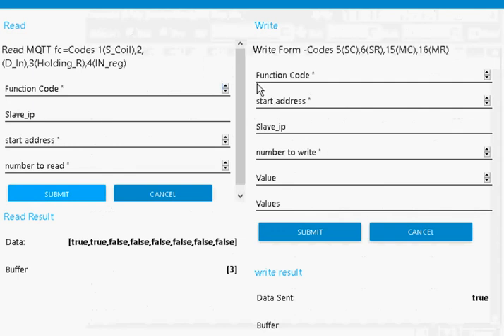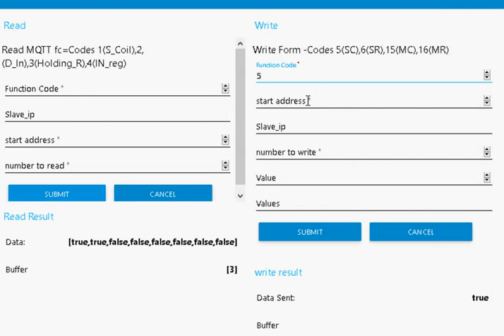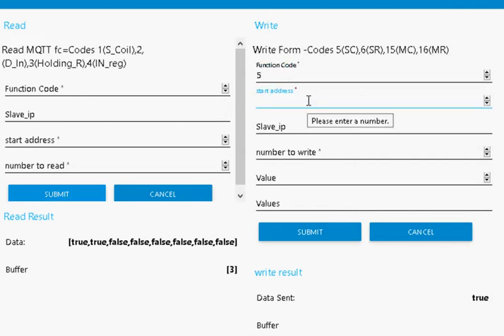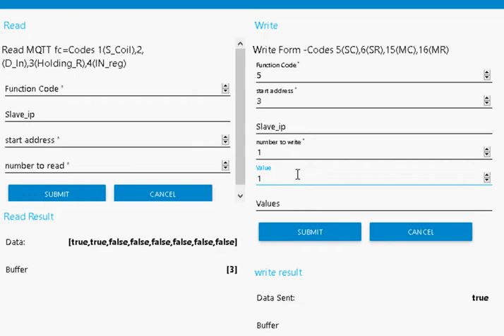Let me show you the writing. To write a single coil, I use function code 5. Start address, I'm going to start at 3, because I'm going to set the third address. I don't need the slave IP. I'm going to write 1, the value is 1. Now I could put 1, 2, 3, it doesn't make any difference. It's really just 0 and 1. 0 is false, 1 and above is true.